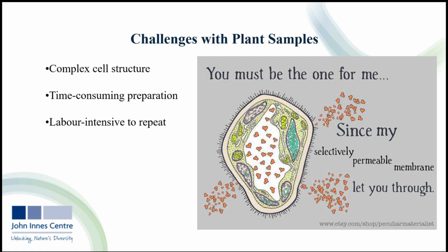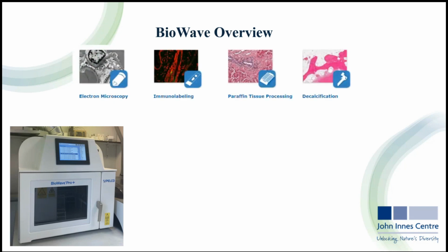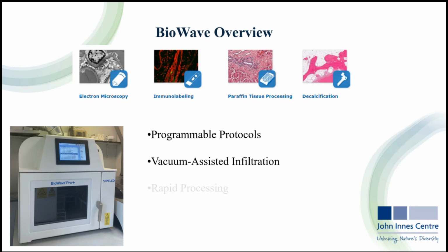This is where the BioWave comes in, and it has the potential to address these challenges. So what exactly is the BioWave? The BioWave is a microwave tissue processor that helps to speed up the embedding process by using programmable protocols, applying a vacuum-assisted infiltration, and this will help to infiltrate the reagents and therefore reduce overall processing times.